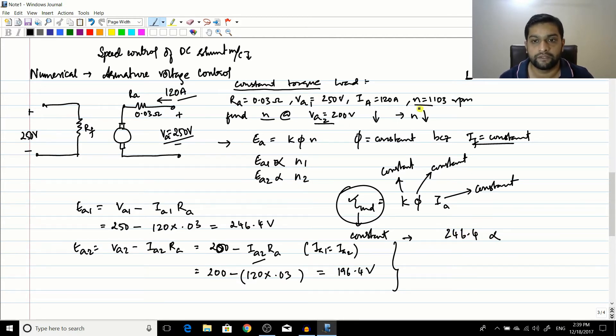I can combine all these things together: 246.4 volts corresponds to N1, so N1 is 1103 RPM, and 196.4 volts corresponds to N2. So N2 will be equal to 196.4 divided by 246.4 multiplied by 1103, and this would give me a result of 879 RPM.